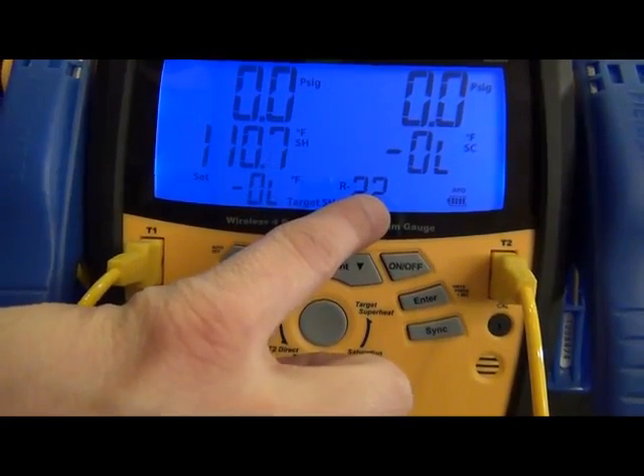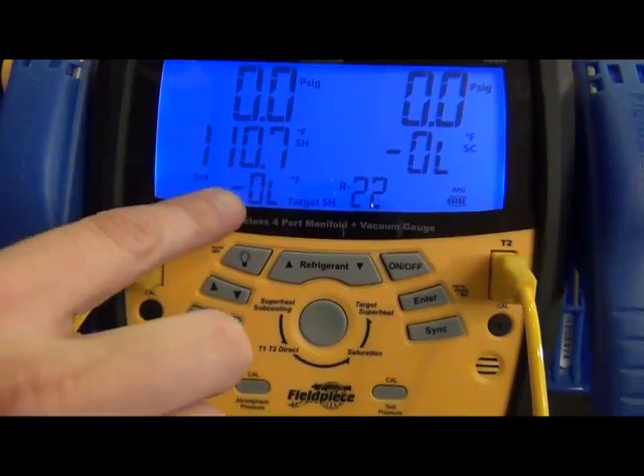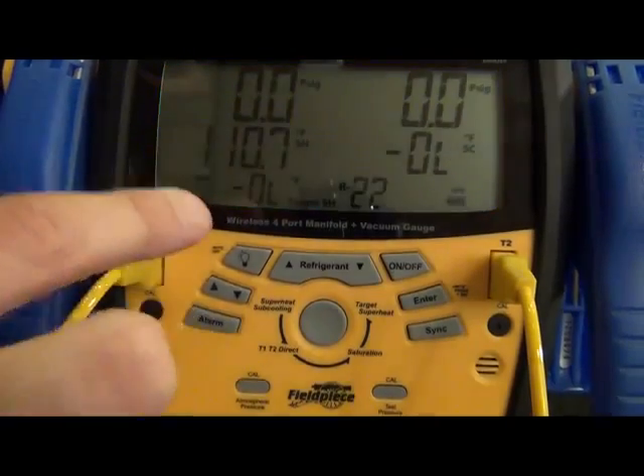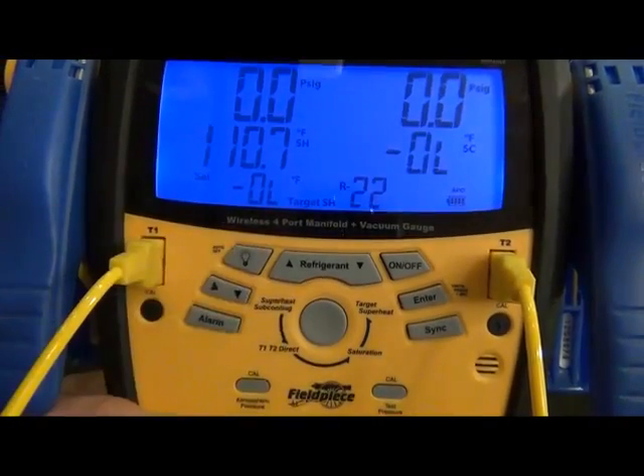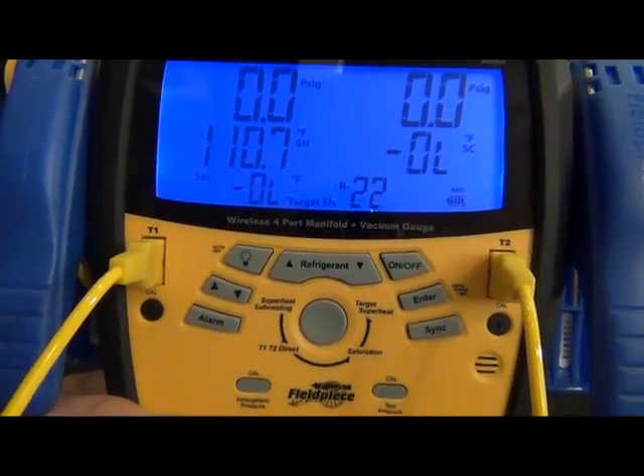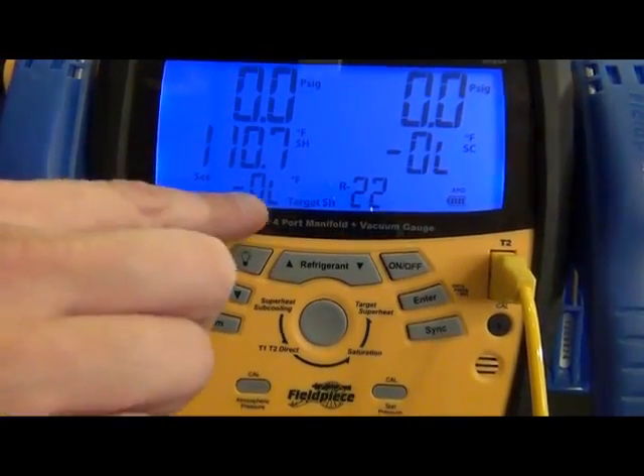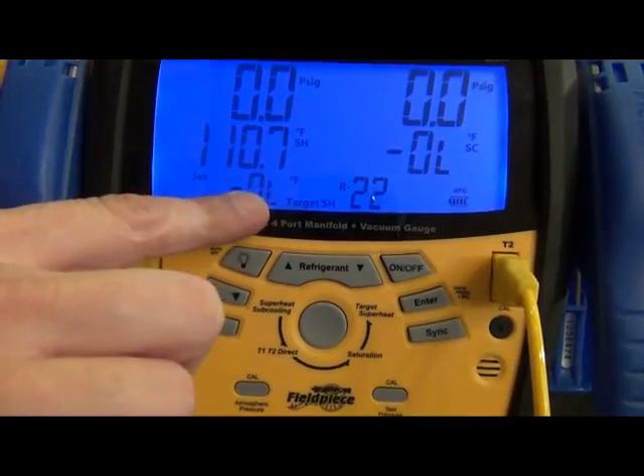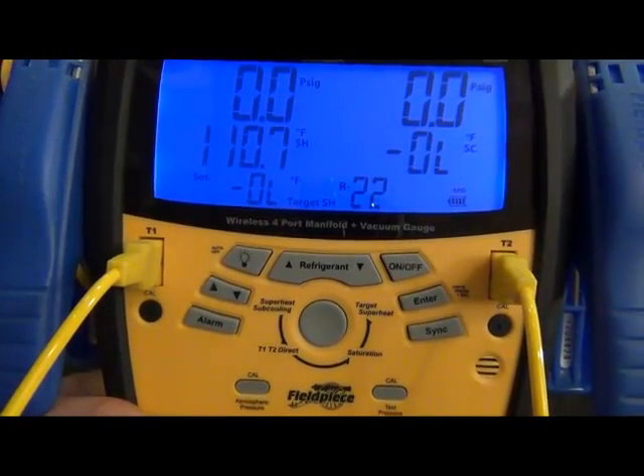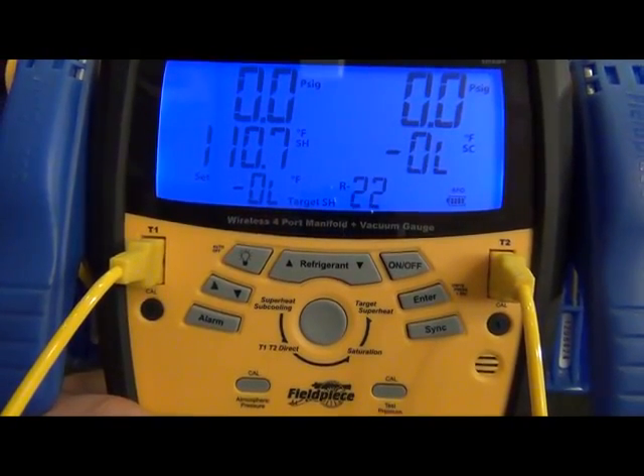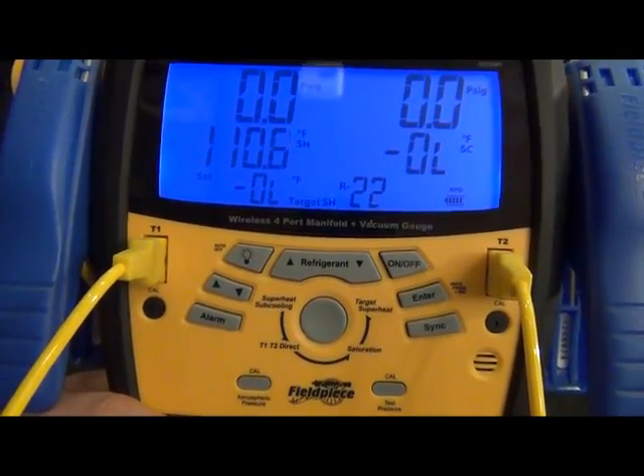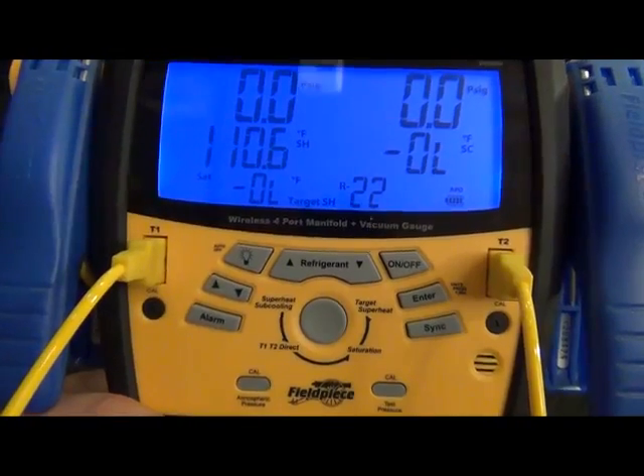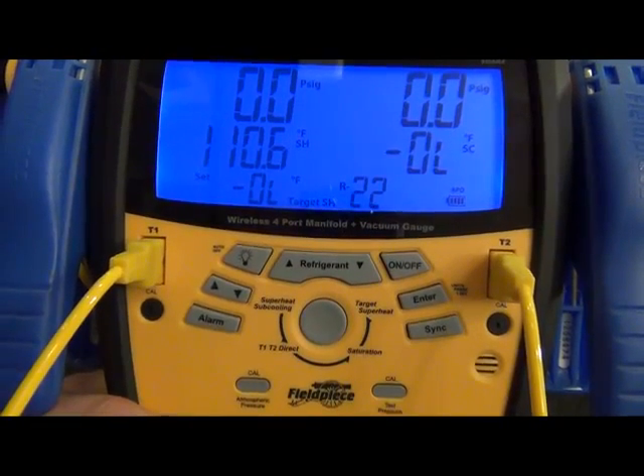It generally will always have your refrigerant, it'll also have your target superheat when you're in superheat and subcooling mode or calculating your target superheat, and right here is also where the microns get displayed when you put it into vacuum. It automatically goes into vacuum once you start pulling a vacuum, so I can't really show it without hooking it up to a pump.